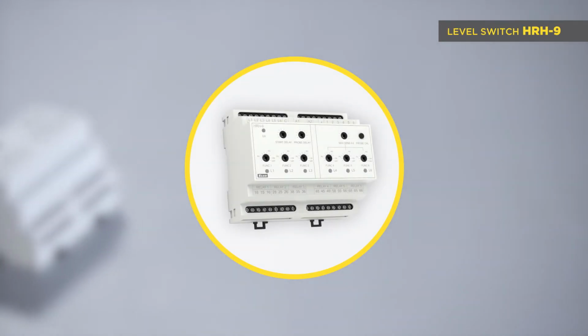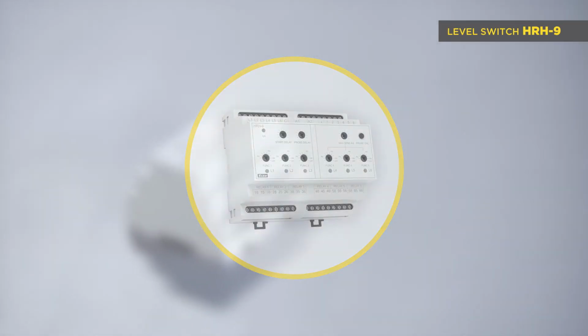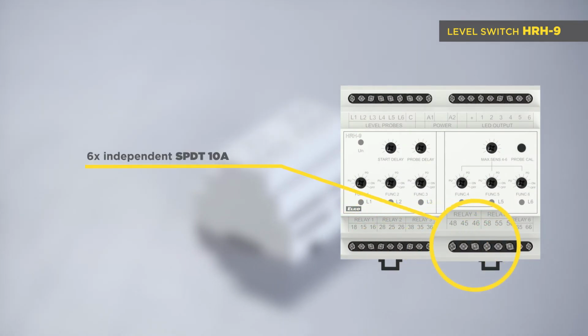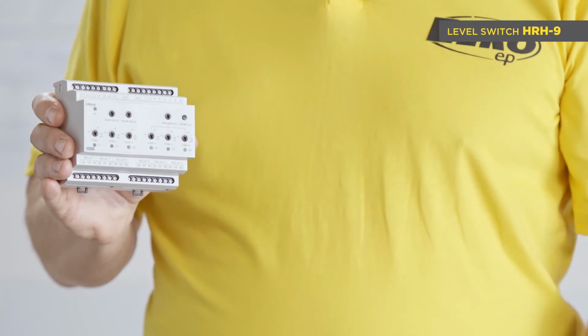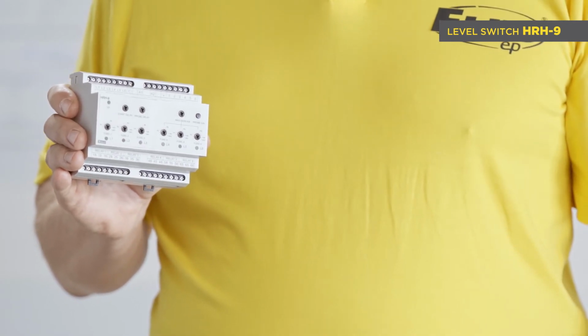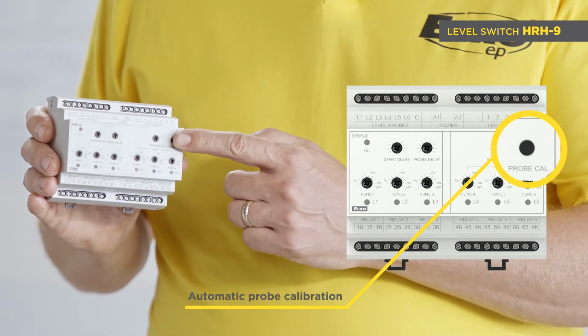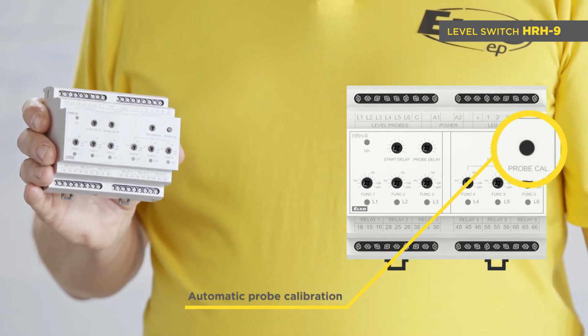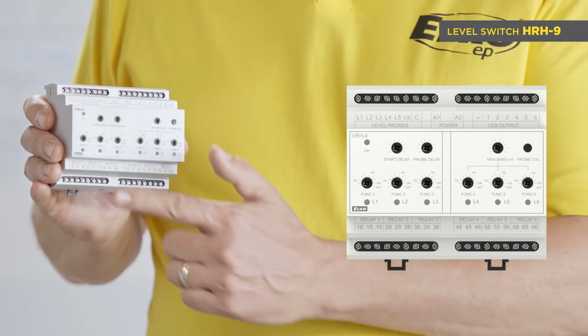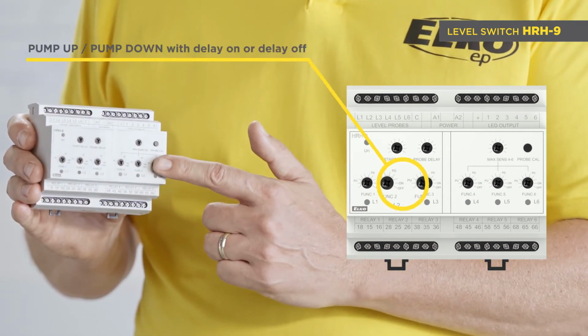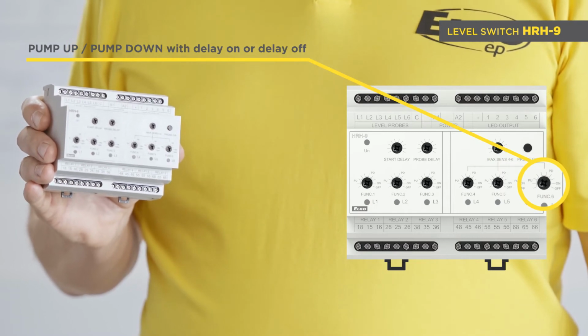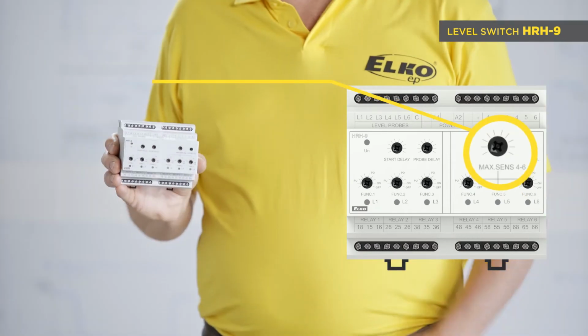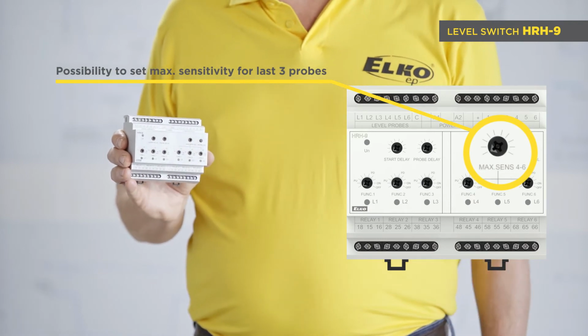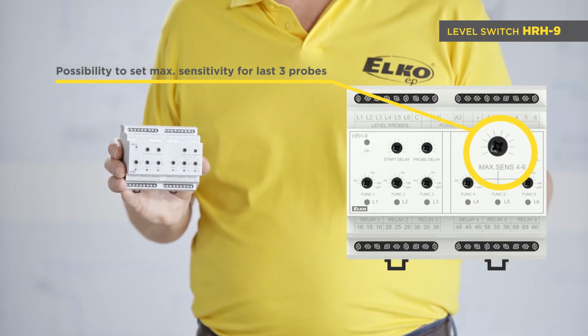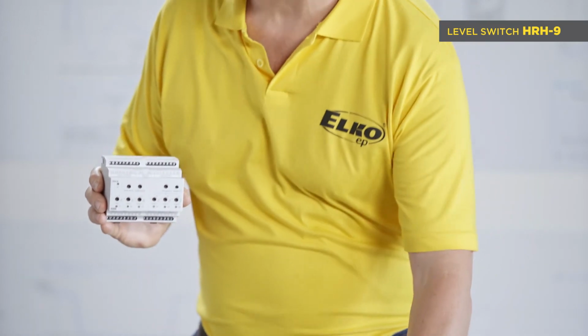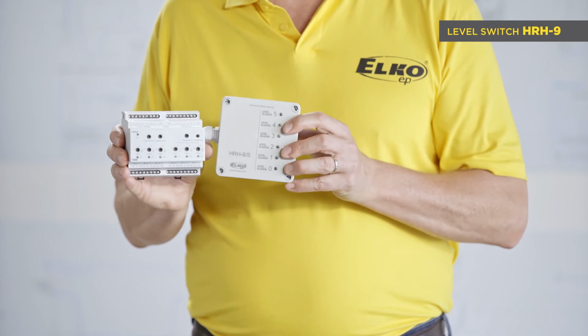HRH9 is similar to HRH6. It has control of 6 liquid levels, but also each level has a dedicated relay for switching pump or auxiliary signalization. Automatic probe calibration is performed by pressing a button on the front panel. There are possibilities to set an independent delay function, master on or off, for each liquid level probe. The LED indicated liquid level is on the front cover of the device. The last 3 liquid probes have possibilities of manually setting sensitivity to account, for example, for foam on liquid. The auxiliary signalization panel, HRH6S, is compatible.